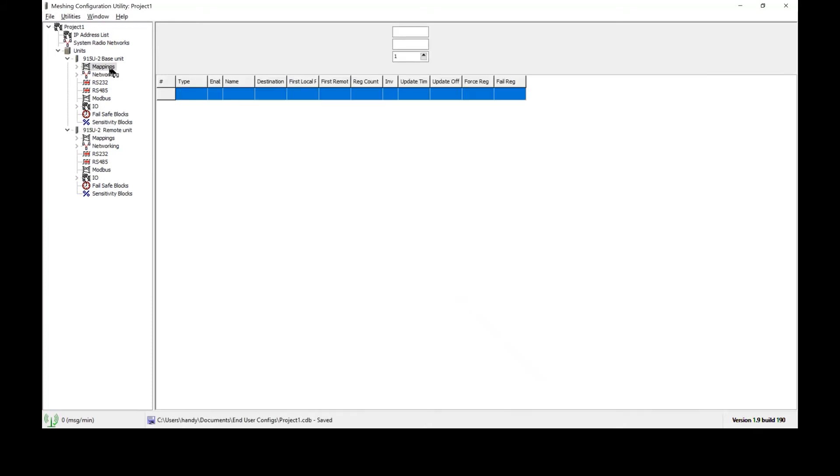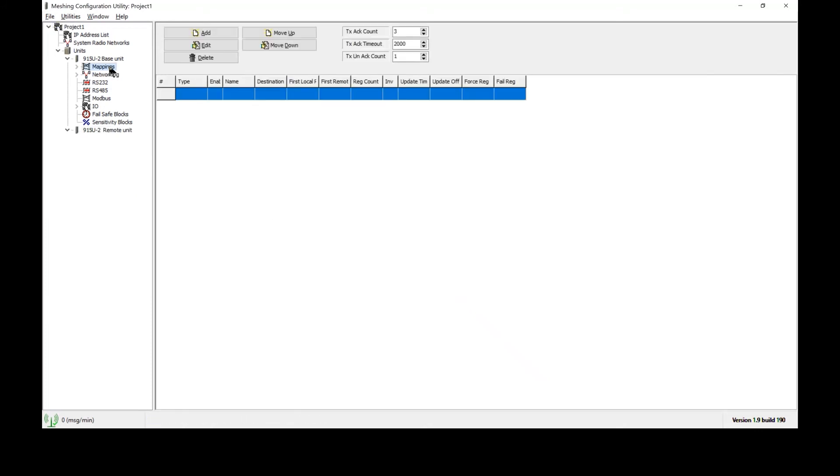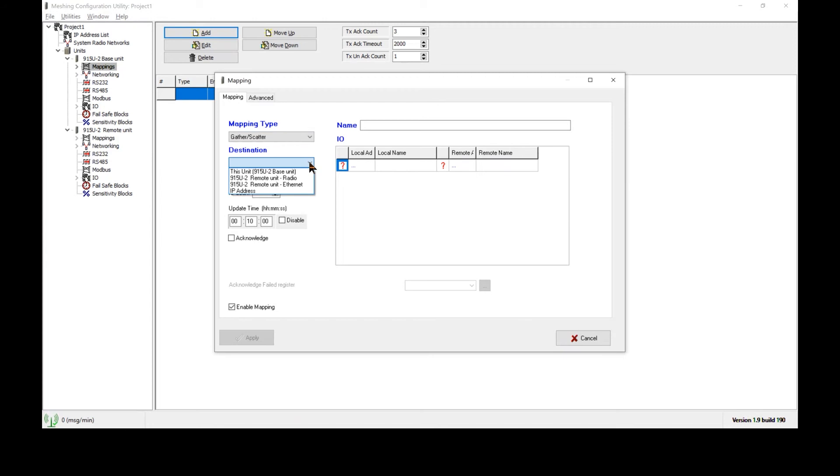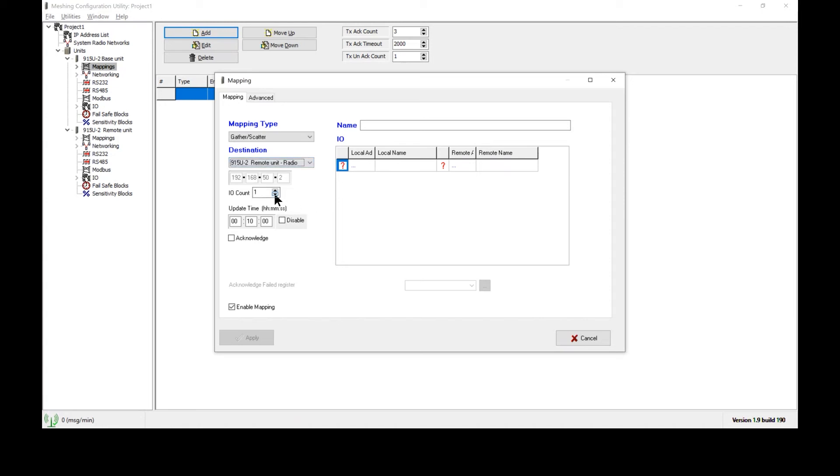Now I'll go ahead and create mappings to wirelessly transmit the 4 to 20 milliamp and discrete signals. I'll select a gather scatter mapping, which allows me to send all of the signals in a single radio transmission. The destination, I will be selecting as the remote unit and the radio port of that remote unit. We are going to send four data points across, so I'm going to set my I.O. count to four. We'll change the update time from 10 minutes to one minute to speed things up a bit.